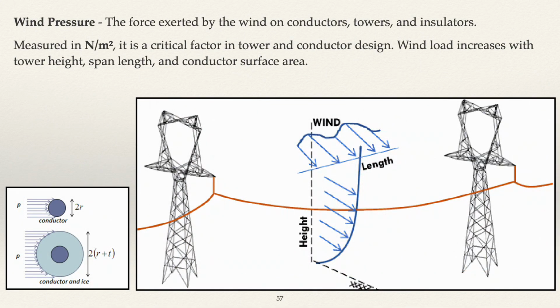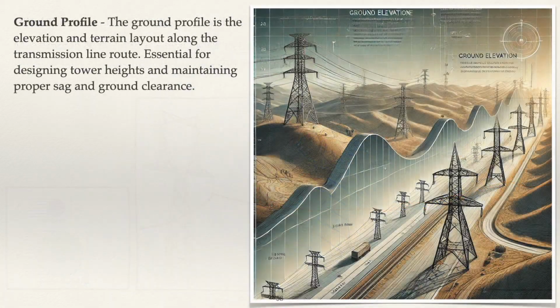Wind pressure. The force exerted by the wind on conductors, towers, and insulators. Measured in newtons per square meter, it is a critical factor in tower and conductor design. Wind load increases with tower height, span length, and conductor surface area. Ground profile. The ground profile is the elevation and terrain layout along the transmission line route, essential for designing tower heights and maintaining proper sag and ground clearance.